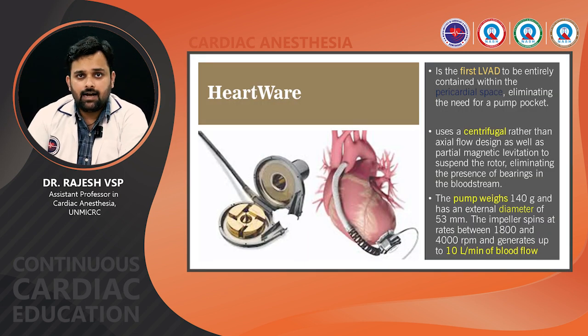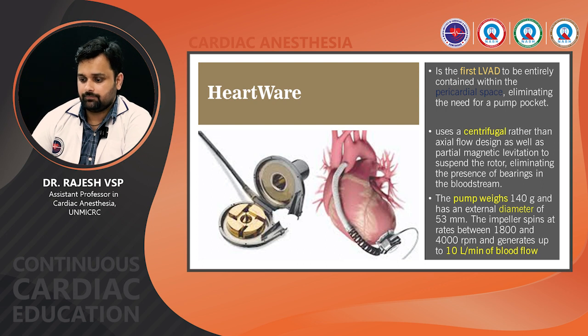In this comes the HVAD. This is the first LVAD to be entirely contained in the pericardial space, eliminating the need for a pump pocket. This uses a centrifugal rather than axial flow design, as well as partial magnetic levitation to suspend the rotor, eliminating the presence of bearings in the bloodstream. The pump weighs around 140 grams with an external diameter of 53 mm, and it spins at 1800 to 4000 rpm, delivering up to 10 liters per minute of blood flow.